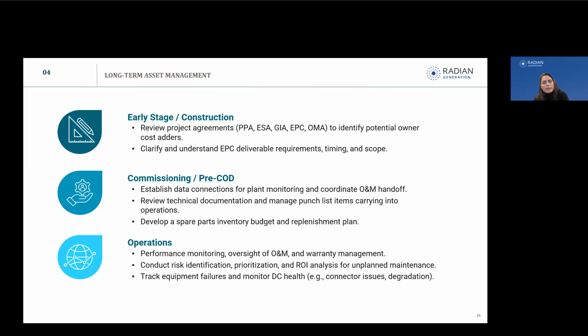Conducting risk assessments and identification, prioritization, and ROI analysis for unplanned maintenance. For instance, an annual substation maintenance might identify an issue that's not causing a production loss but is at risk of critical failure. That might not pop up as a priority for the O&M since it isn't creating a generation loss at the time, but the risk is there to take the whole plant offline. Asset managers can help identify and prioritize those issues, working with the O&M to make sure they're taken care of before something bad happens.